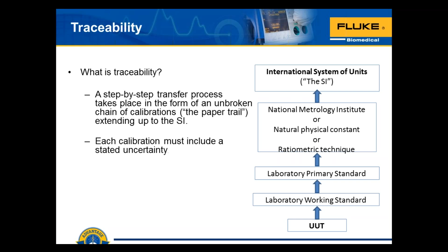So when you look at Fluke or Fluke Biomedical, we are not always traceable. We're not traceable to NIST at all. We are traceable to the SI. We are traceable to the SI sometimes through NIST, for example, but we may be traceable through other NMIs as well in order to get back to SI. And that's how we define our traceability, and you can ask, and we should be able to tell you what our traceability is, just as you should be able to, when asked, tell what the traceability chain is for your test instrument.